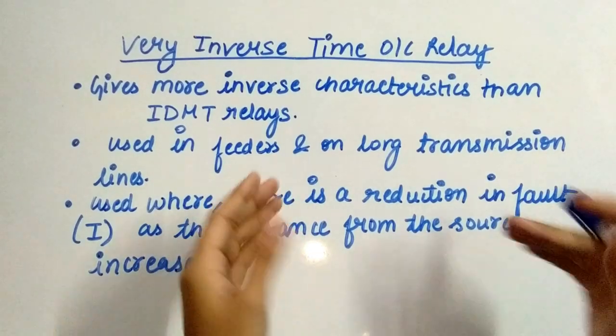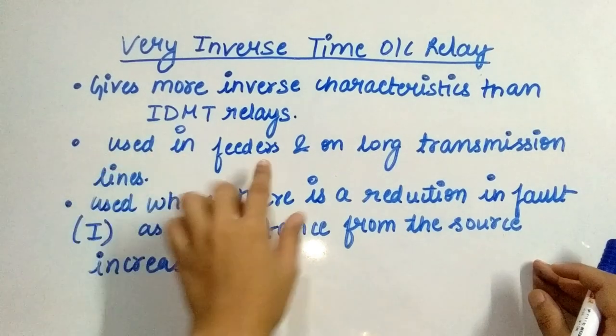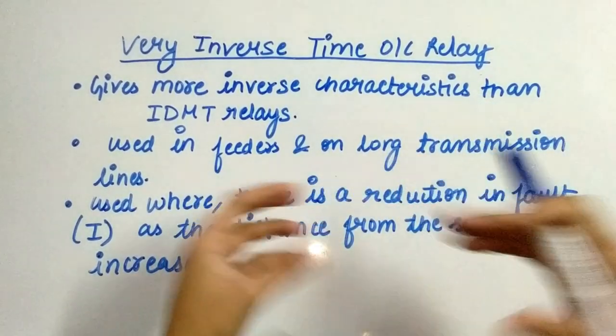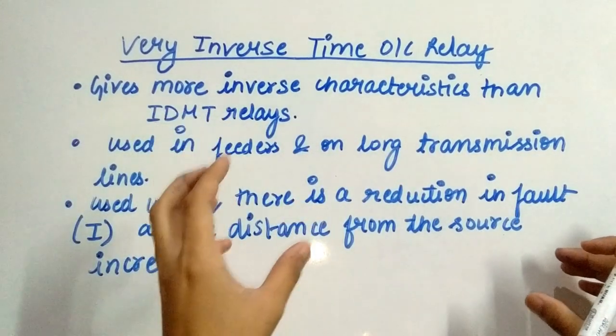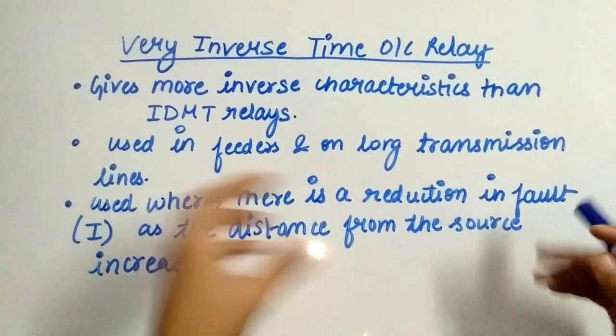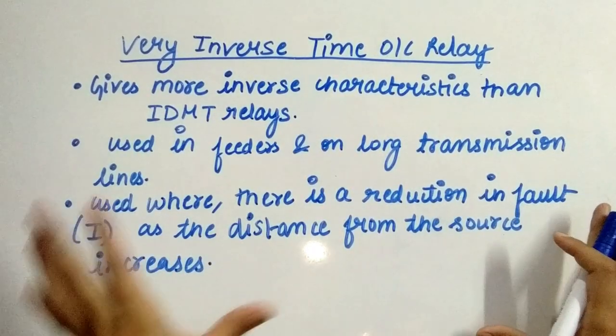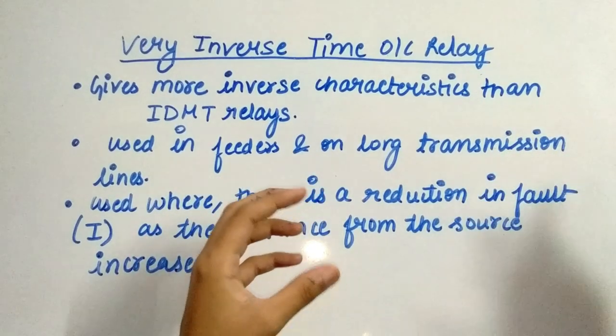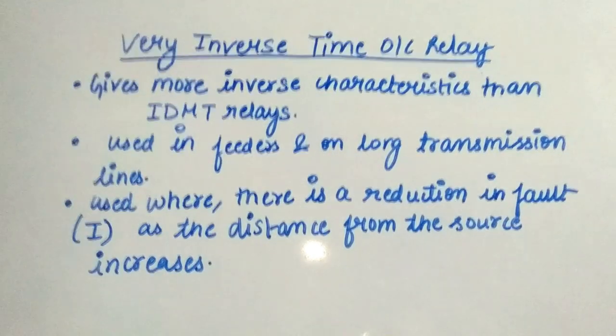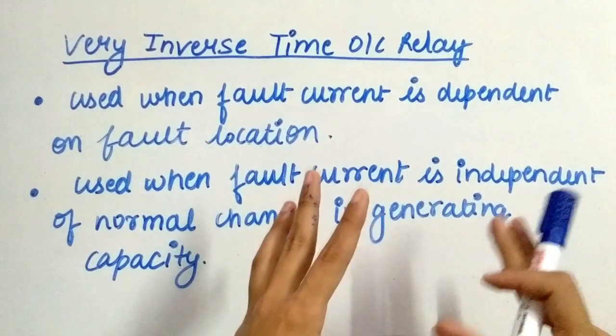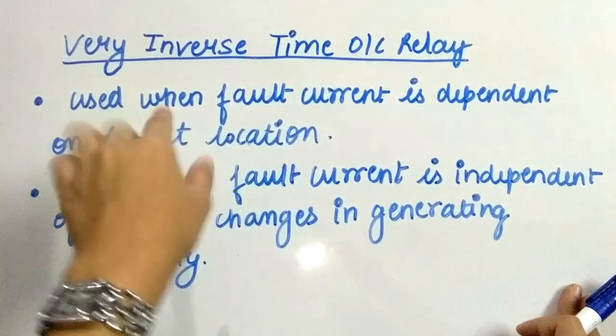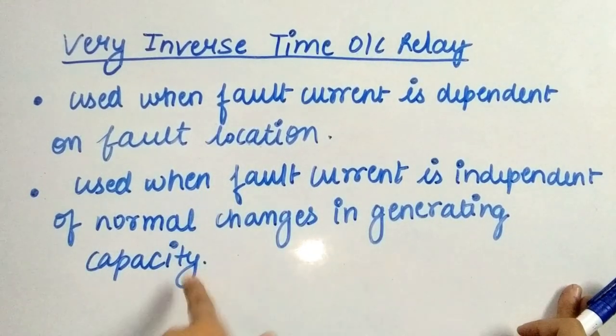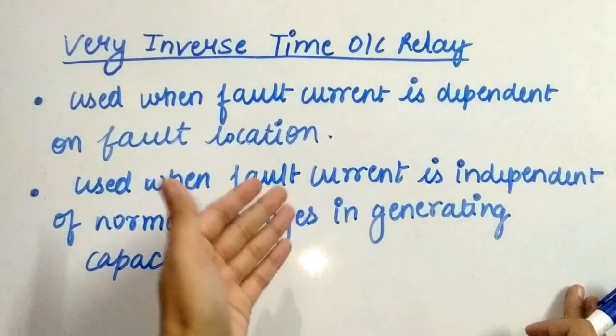Very inverse overcurrent relays provide more inverse characteristics than IDMT relays. They are used in feeders and on long transmission lines, particularly where there is a reduction in fault current due to increasing distance from the source. They are particularly suitable if the short circuit current drops rapidly with the increase in distance from the substation. Very inverse time overcurrent relays are used when the fault current is dependent on the fault location, and when the fault current is independent of normal changes in generating capacity.